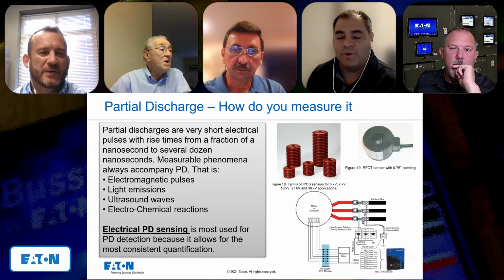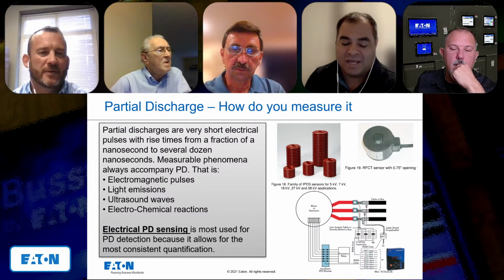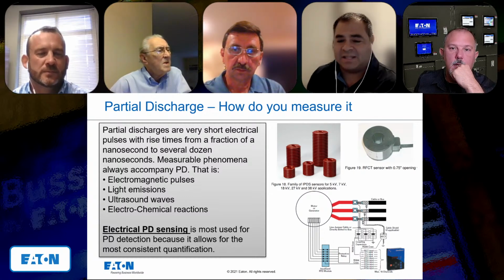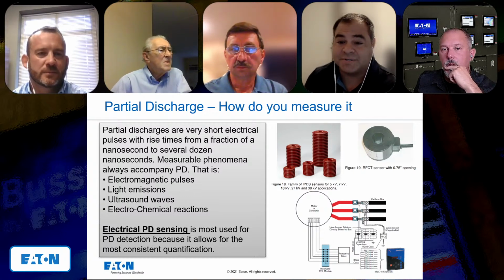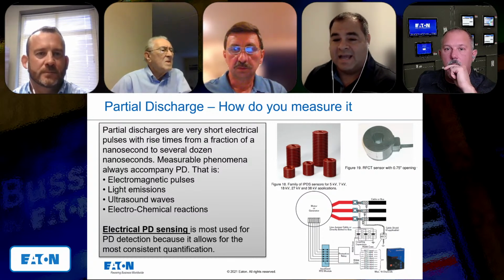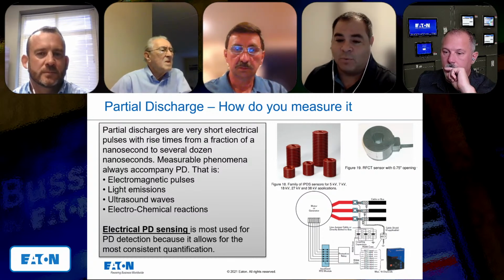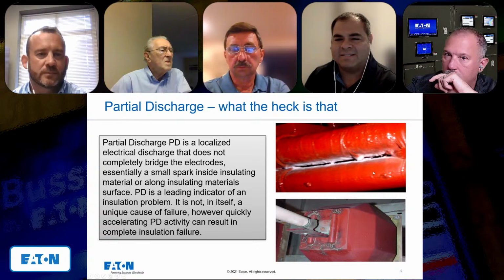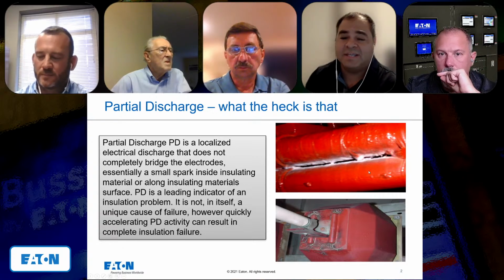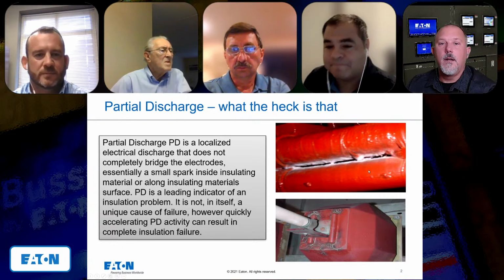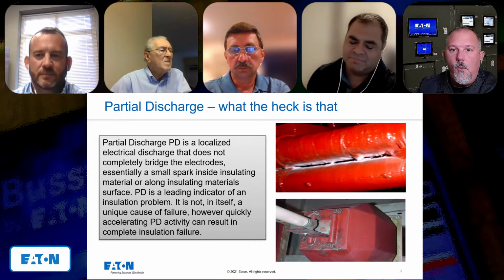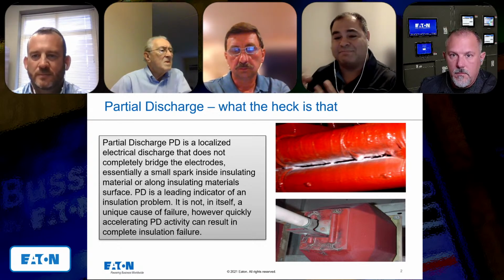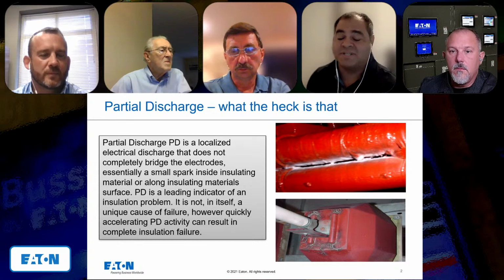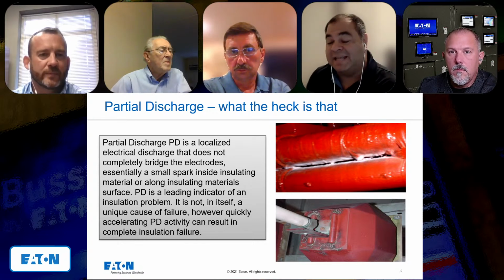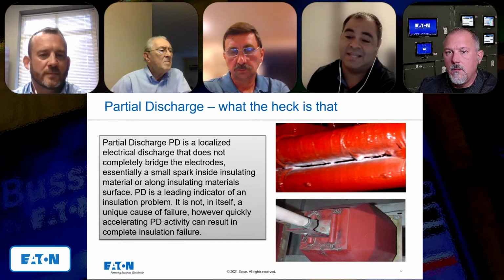You could have equipment with a low-level partial discharge that could be working for years. And like the picture with the white powder, that's a motor winding probably. So in motors, because of the design and the space you have there, you always have partial discharge, and they design the insulation to withstand that.